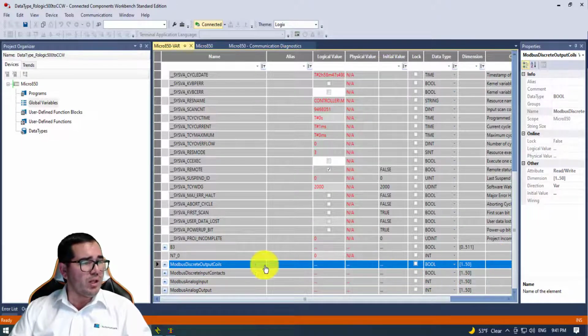So I put it like this here. Let's say Modbus discrete output coils, I put between 1 to 50, and 1 to 50 for each of the others over here, like you can see. The first two here are discrete output and discrete input, and the last two are analog input and analog output. So I created them as int and int here.